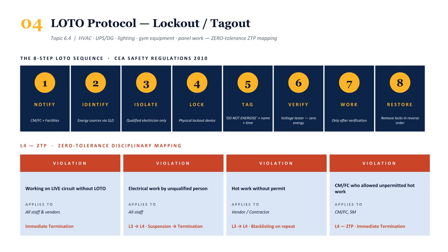Step 3. Isolate, performed only by a qualified electrician under CEA Safety Regulations 2010. Step 4. Physical lockout device applied to the breaker in the off position. Step 5. Tag with Do Not Energize, Maintenance in Progress, person's name, date and time. Step 6. Verify with a voltage tester to confirm zero energy. Independent verification, not assumption. Step 7. Work proceeds only after verification. Step 8. Restore in reverse order, with CMFC notified before re-energizing.